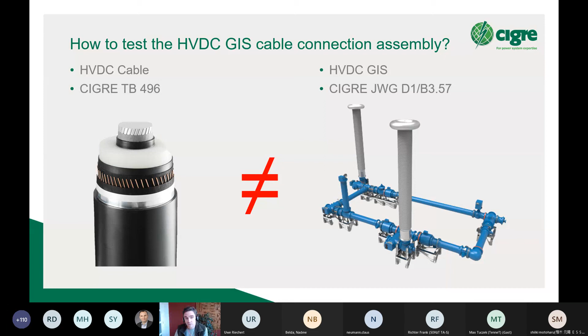To be a little bit more specific about the differences, in a very crude comparison, you could say that the HVDC cable test philosophy is to test the cable's ability to withstand the operational stresses that are applied to it during service time, and also the aging that takes place over the cable's lifetime. When you look at the HVDC GIS related tests, they are more focused on testing the GIS ability to withstand the operational stresses, but not so much aging phenomena, as this doesn't take place as much as in cables.